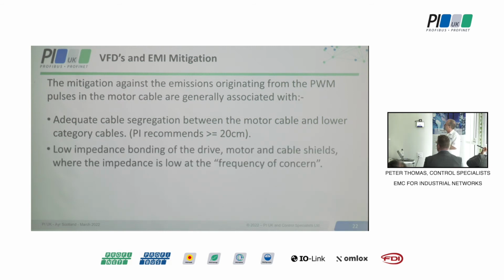Then there is a low impedance bonding of the drive, motor cable, and the motor and cable shields, where impedance is low at the frequency of concern. When most 50, 60 hertz people see the word bonding, they're generally thinking of green and yellow wire. But whenever you see green and yellow wire, that is safety bonding. I'm not here to tell you anything new about electrical safety, but if you've got a bonding infrastructure that is full of green and yellow wire everywhere, it will be completely safe and meet the electrical safety standards, but it will not give you an EMC compliant bonding infrastructure. You might get away with it, but those are the kind of things that we need to improve.